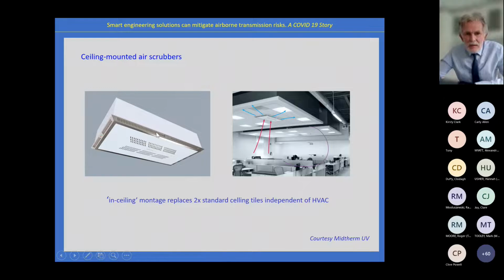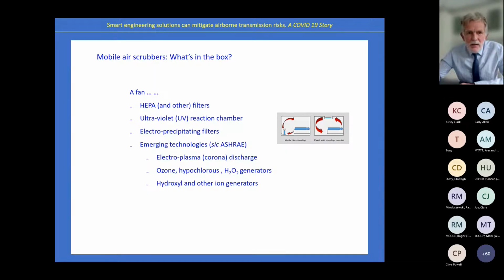A nice piece of kit that came out about 6 months ago mounts on the ceiling. It doesn't directly interface with the HVAC — it's simply a recirculation device that replaces 2 ceiling tiles. I like this because it's out of the way, so people don't trip over it, and it can be installed in literally 2 or 3 hours, so there's no interruption to clinical flow if done out of hours. Okay, let's look at what's in the box.